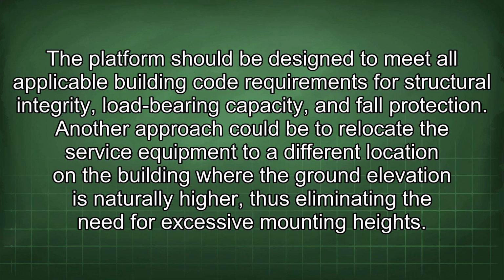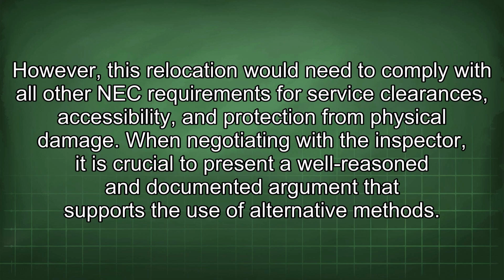Another approach could be to relocate the service equipment to a different location on the building where the ground elevation is naturally higher, thus eliminating the need for excessive mounting heights. However, this relocation would need to comply with all other NEC requirements for service clearances, accessibility, and protection from physical damage.